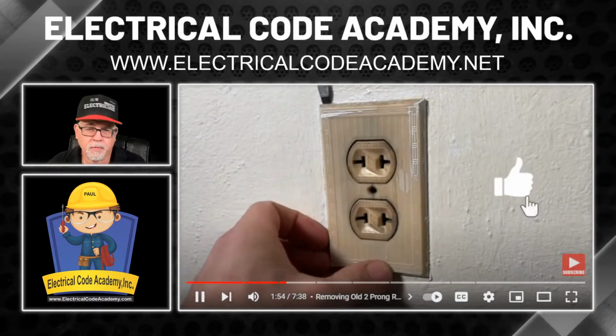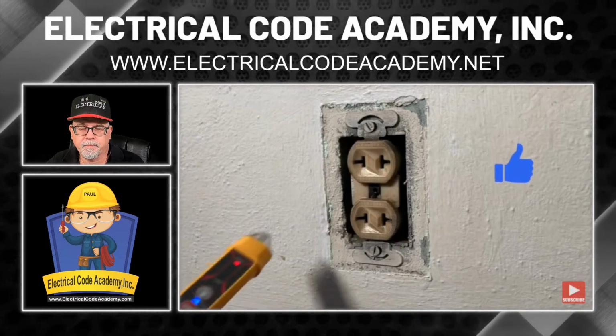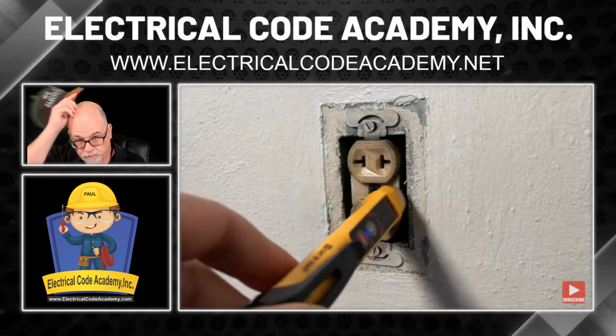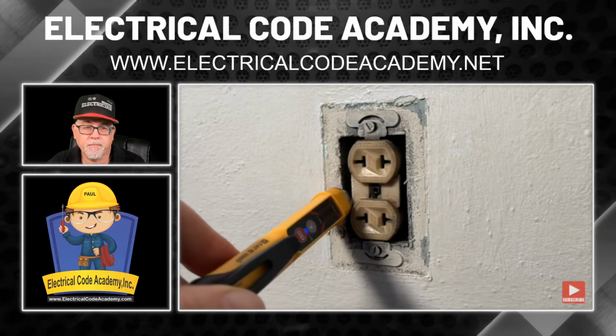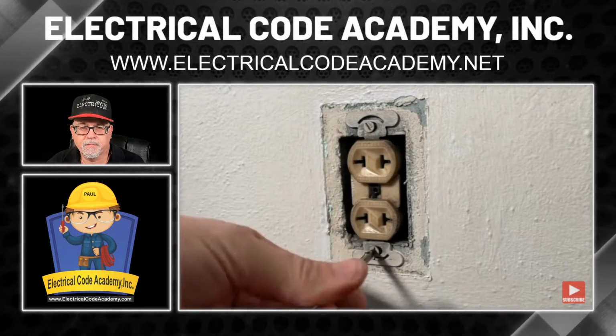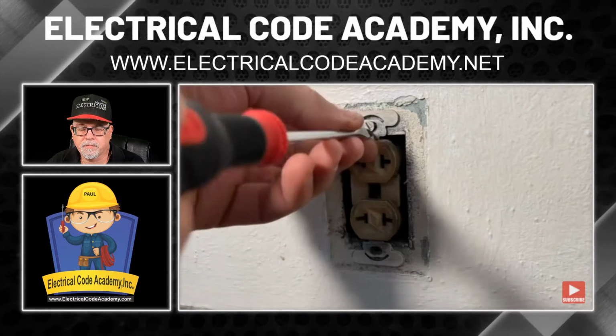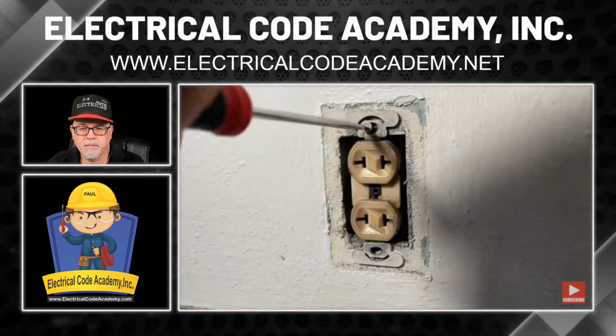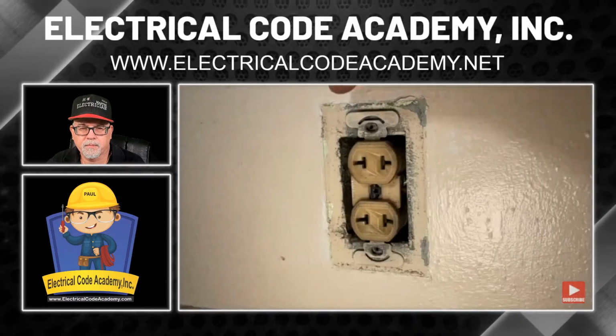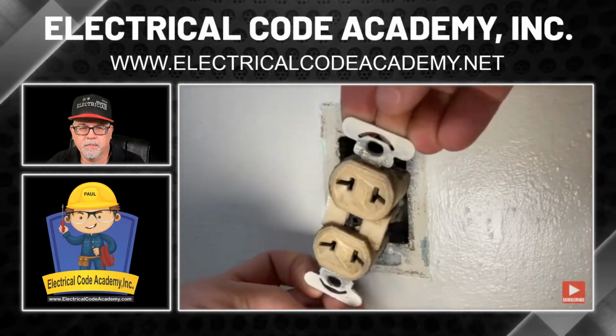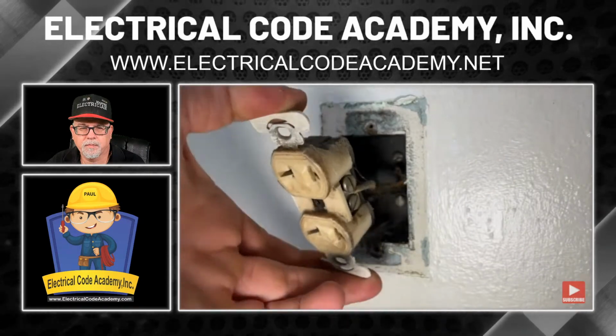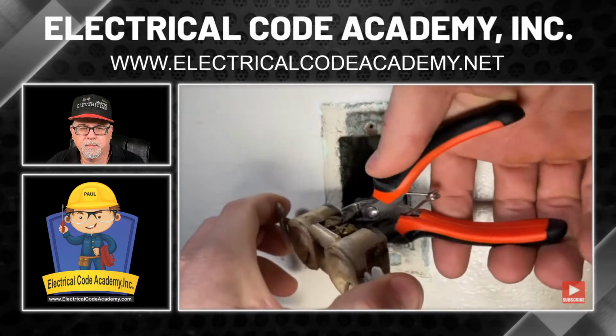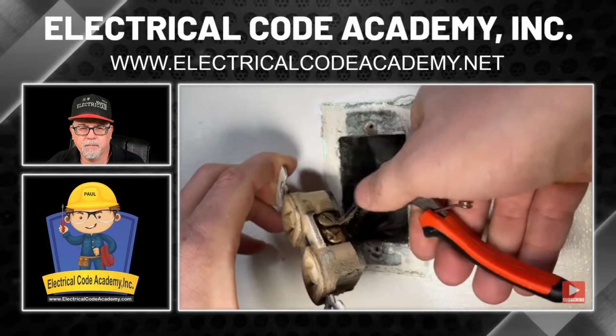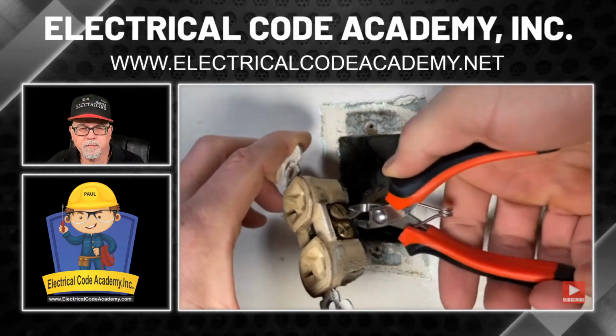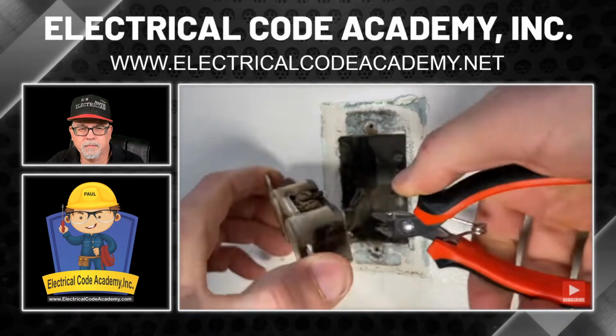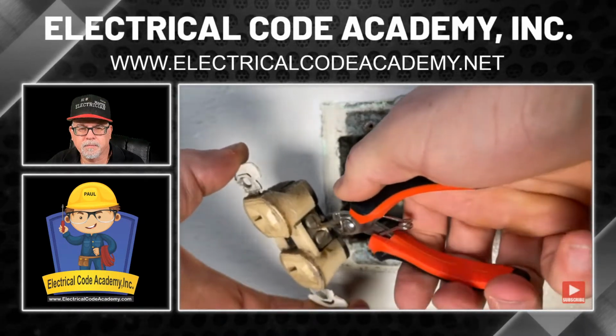Then I undo the screw and carefully remove it to reduce any paint damage. Just double check in here to make sure that no power is going to the box. Then I'm removing the 2 mounting screws so I can pull the old 2-prong receptacle out. And we'll take a look at what we're dealing with. And here, you really only expect to see a neutral and a hot side. So I am going to take my micro side cutters and then just cut that off clean so we can strip new copper for the GFCI.